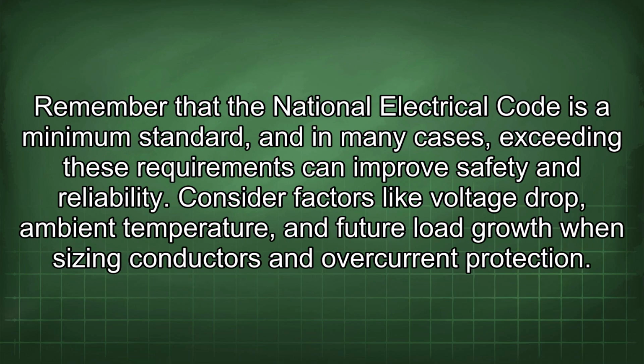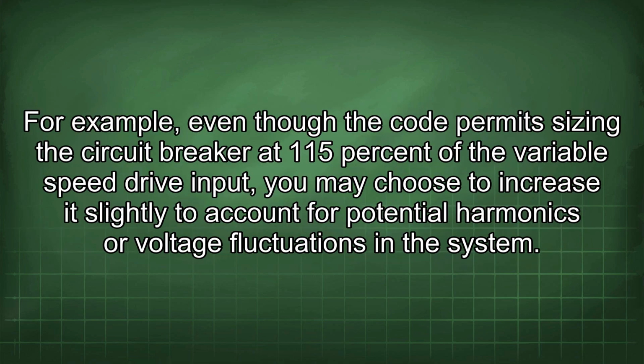Remember that the National Electrical Code is a minimum standard, and in many cases, exceeding these requirements can improve safety and reliability. Consider factors like voltage drop, ambient temperature, and future load growth when sizing conductors and overcurrent protection. For example, even though the code permits sizing the circuit breaker at 115% of the variable speed drive input, you may choose to increase it slightly to account for potential harmonics or voltage fluctuations in the system.